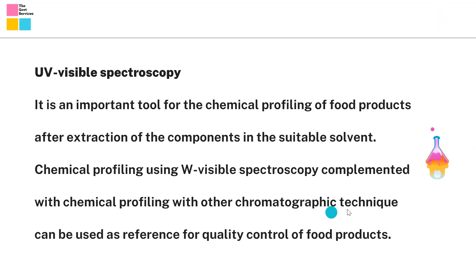So now, normally what happens is, if you see here, the UV light or visible light is passed through this instrument. This is the inside of the spectrometer. So this diagram, guys, is the inside of the spectrometer, nothing else, right? So now you load the sample here in sample cuvettes, right? You might know what a cuvette is. A cuvette is just a small test tube, you can call it. So the sample is loaded in this cuvette, right? This is the reference cuvette and this is the sample cuvette.